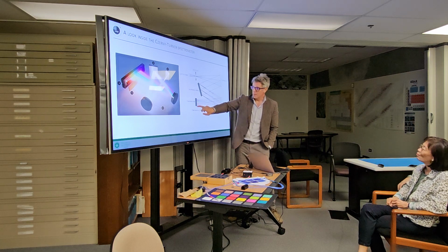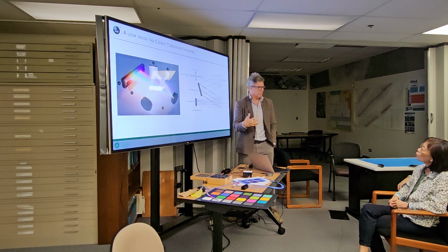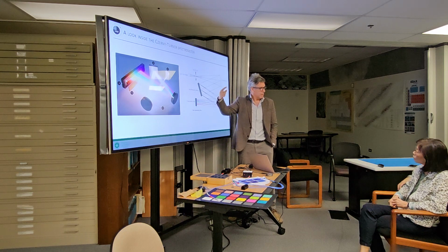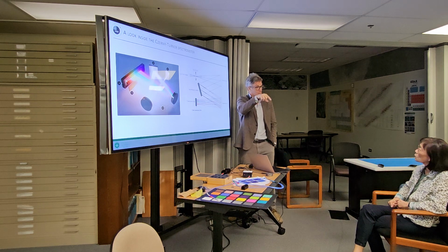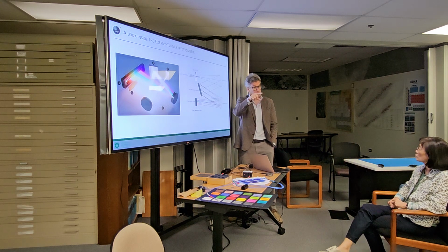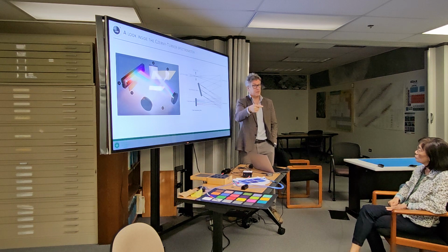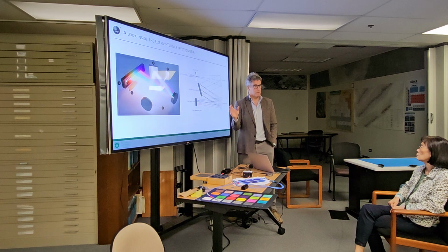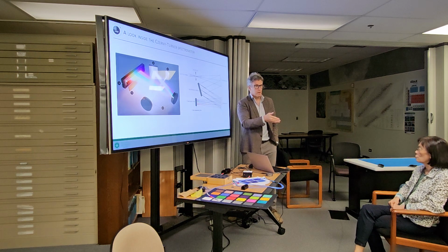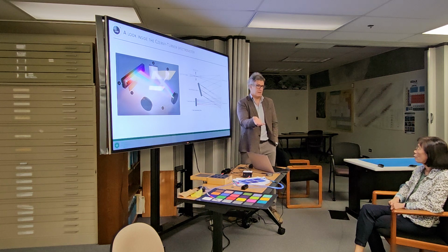The other thing is this order separating filter. If you remember, I said with these diffraction devices, the rainbow repeats and repeats. Most of the energy, like the interference patterns that you've probably all seen, is in the big blip in the middle, right? But then we have those limbs and bumps on the edges where we have the second order dispersion, and we need an order separating filter so that we don't count that light, right? Because we're trying to count photons, and if we're counting more photons than we should count, then that's bad.